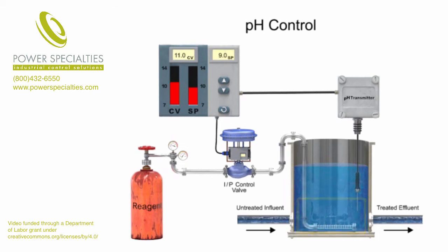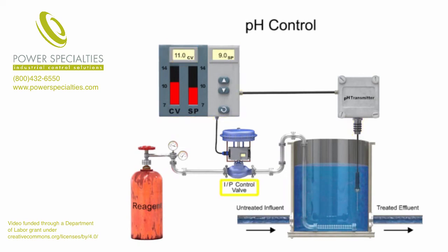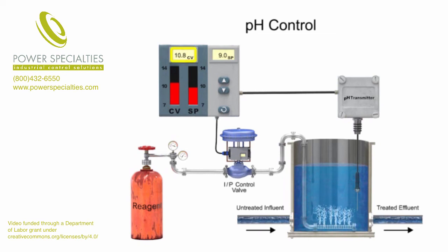With the pH level at 11 detected by the sensor, the controller commands the control valve to open and introduce more carbon dioxide. As the increased carbon dioxide mixes with the influent, the pH is lowered in a controlled manner.